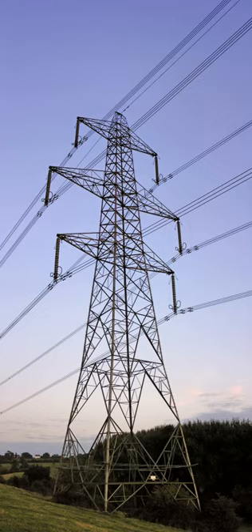Indeed, for economic reasons, some transmission lines are designed for three or four circuits, but only two or three circuits are initially installed. Some high-voltage circuits are often erected on the same tower as 110 kV lines. Paralleling circuits of 380 kV, 220 kV and 110 kV lines on the same towers is common. Sometimes, especially with 110 kV circuits, a parallel circuit carries traction lines for railway electrification.